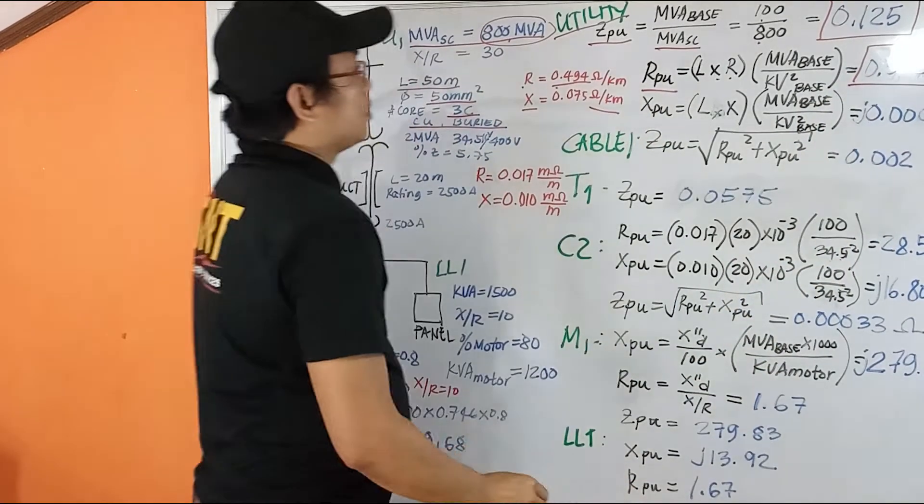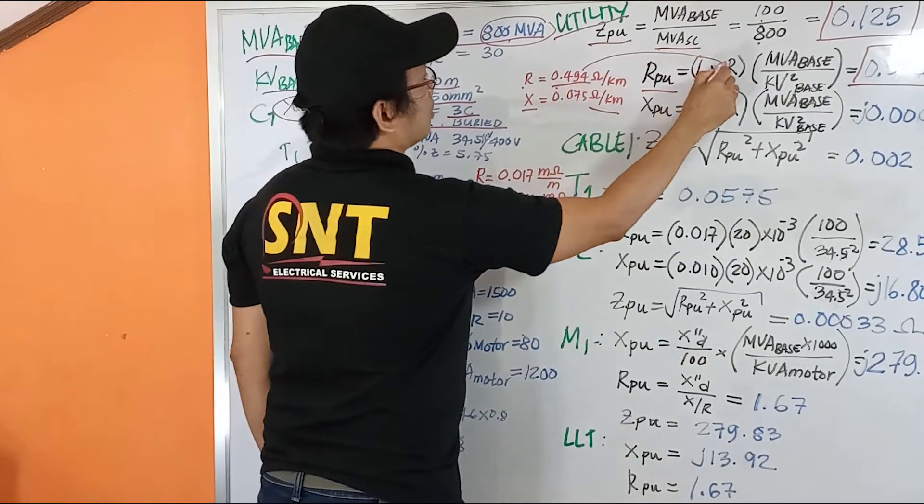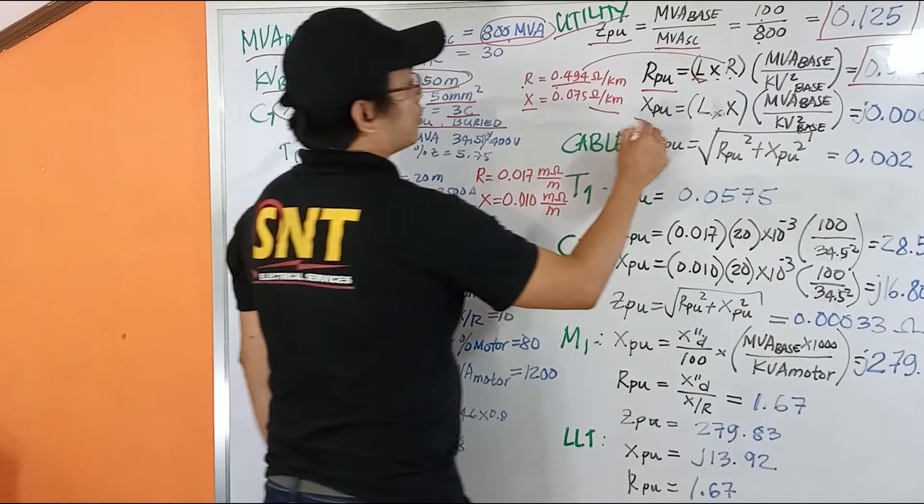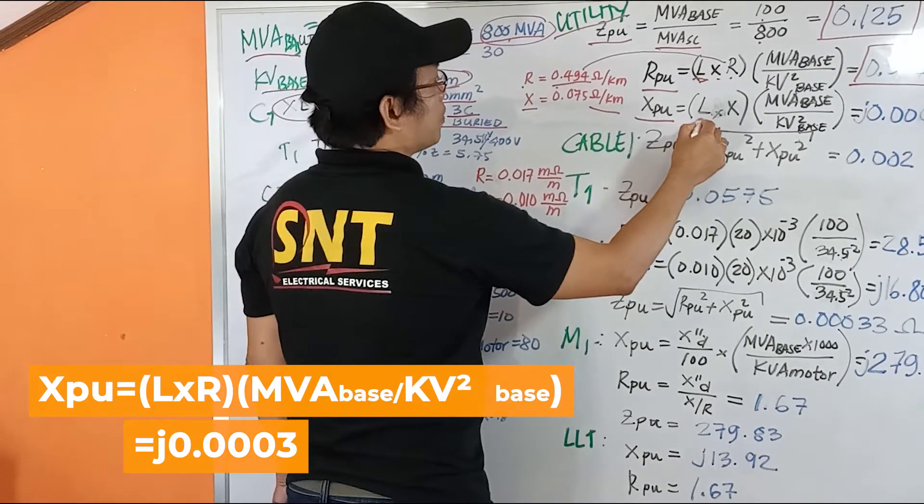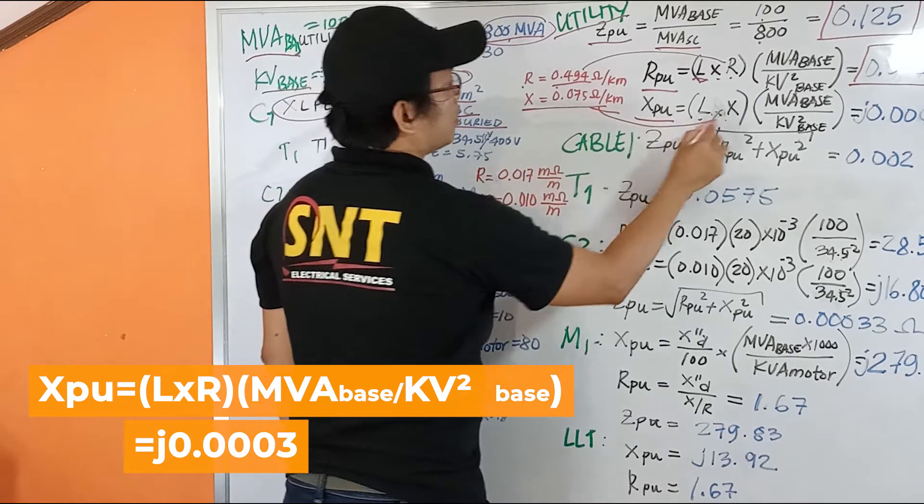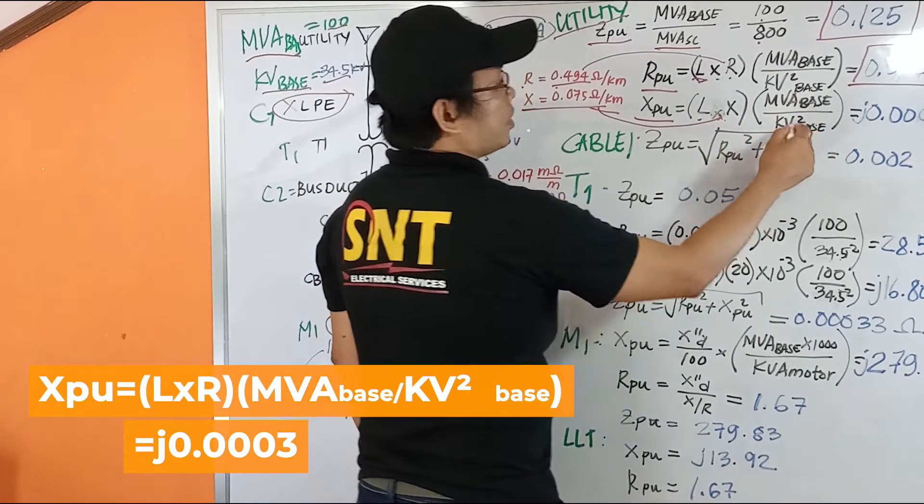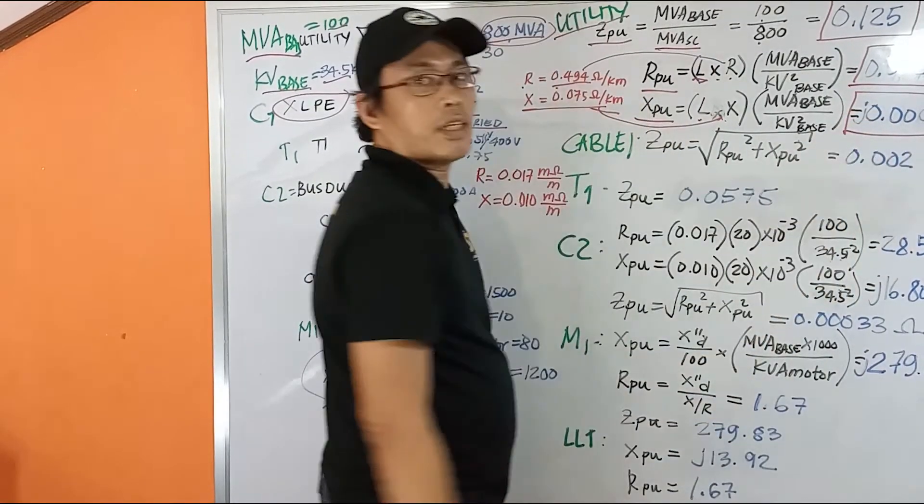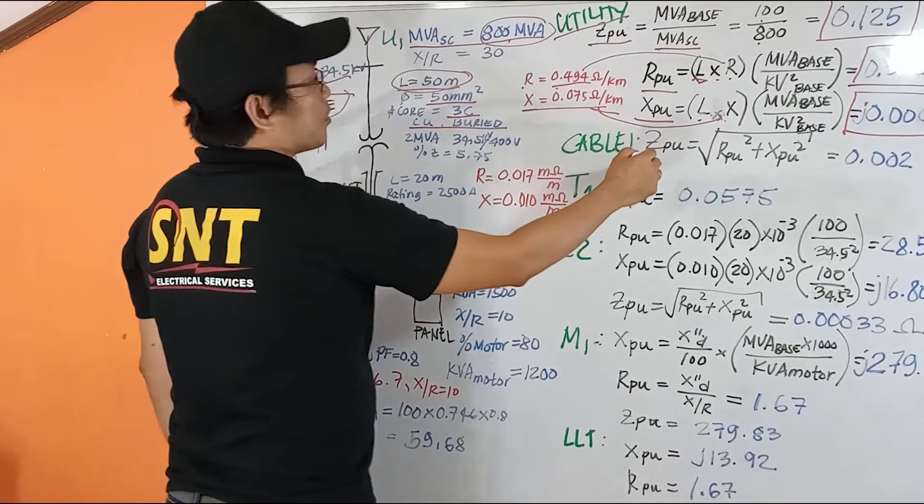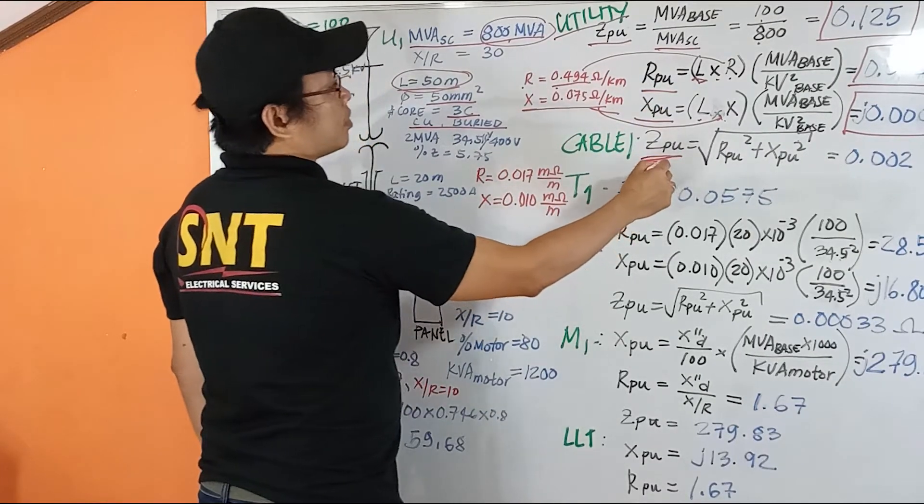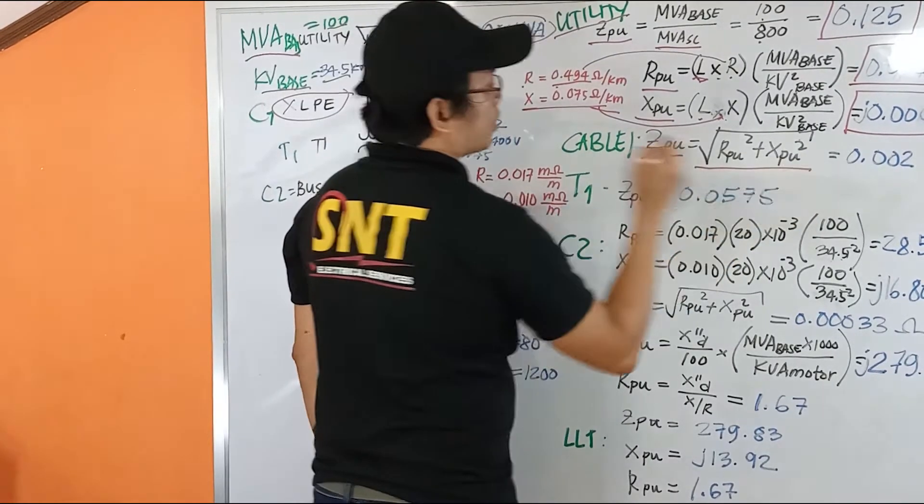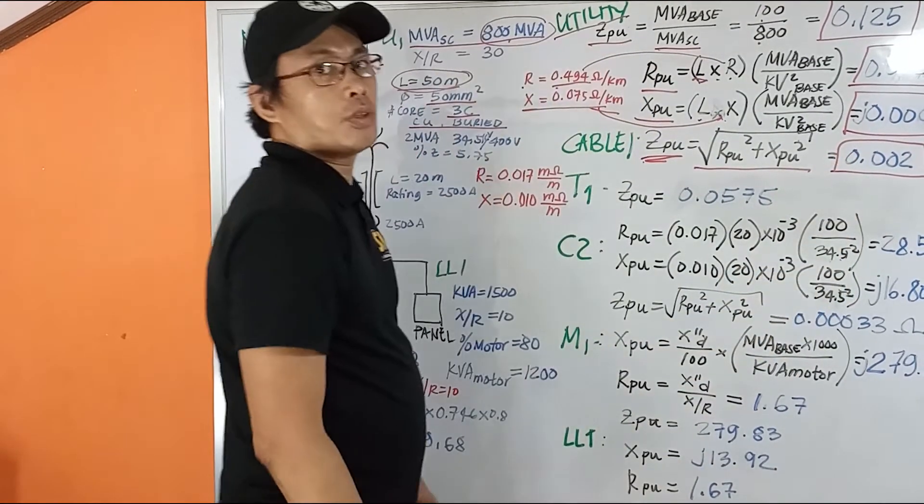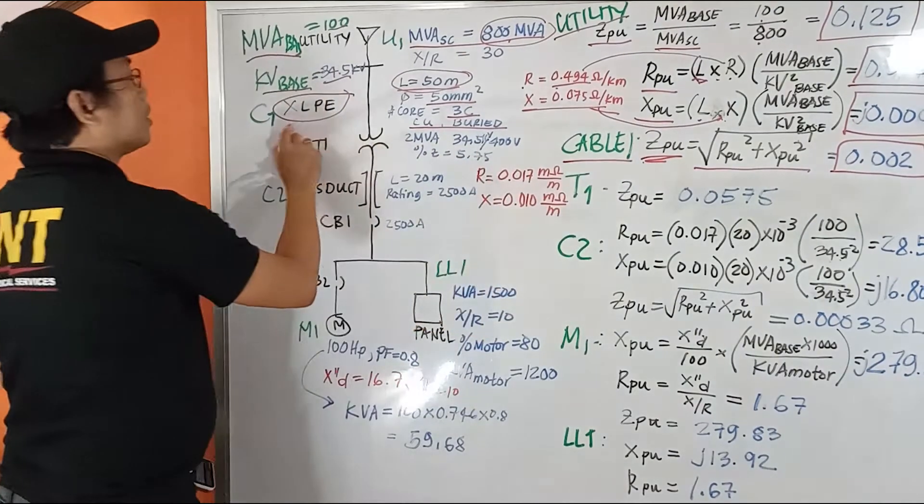So our R here, and our length is 50. In the same manner, our reactance per unit, we have the length 50 times this value here. Then MVA base over the kV base, the voltage squared, and we get this value. 0.002. That's for our cable number one here, the XLPE.